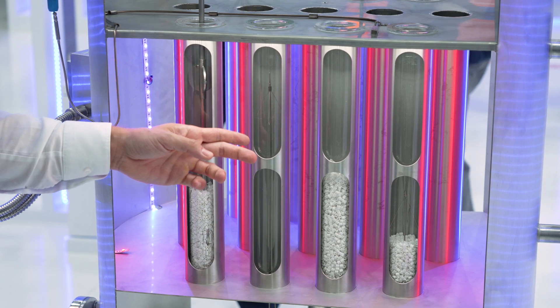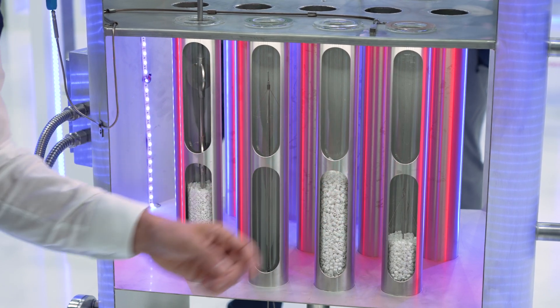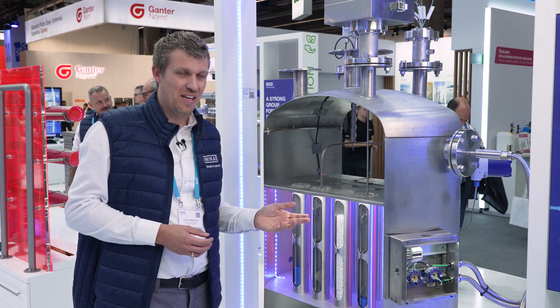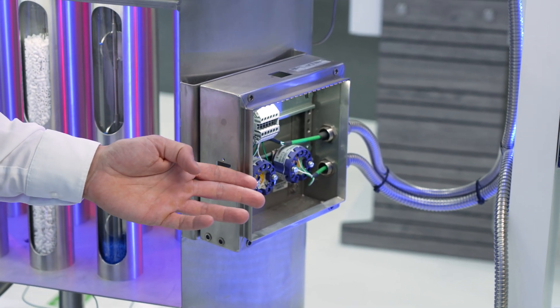The multipoint sensors are positioned at different heights and give the operator a detailed view on what is going on in the reactor. The signal from the individual points is transmitted via temperature transmitters which are SIL2 certified, ATEX approved, and capable of operating with HART to the operator's room.